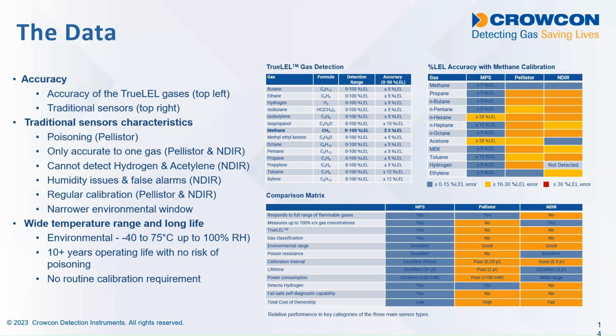So an infrared sensor calibrated for methane will detect propane or butane or pentane, but it will be wildly inaccurate. It will massively over-respond. So the reading you get will be a much, much higher concentration than is actually present. And as we've discussed before, the infrared sensor can't detect hydrogen at all. So we're left with the Pellistor conventionally, but the problem is Pellistors get poisoned, and they really do. So you have to gas test them all the time to be sure that they remain operational.